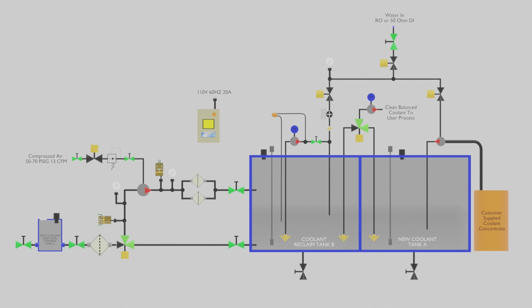When the auto balance controller determines levels in both tanks are optimal, the controller opens the emergency backup main normally closed water solenoid. Subsequently, the solenoid controlling the incoming Tank A water supply also opens, directing water to the proportioning pump. Pressurized water now flows to the proportioning pump, energizing it. Following the previously outlined process, the pump then pulls coolant concentrate from a customer-supplied container, blends it with the incoming water, and delivers perfectly mixed coolant into Tank A.